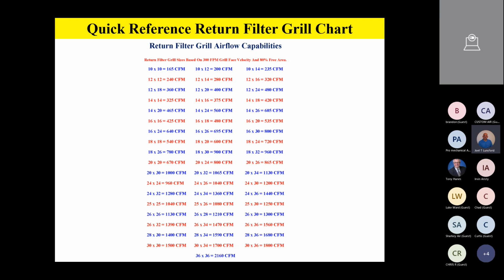of that grill and 300 feet a minute grill face velocity, that's the maximum velocity Manual D recommends for the air moving across the filter. If you've got a filter in that grill, they don't want you exceeding 300 feet per minute across that filter. The higher the velocity, the less efficient that filter works. And so based on all the Manual D criteria I've just mentioned, this is a quick sheet to help you say, well, gee, I wonder how much air a 20 by 20 filter grill is actually moving. In our example here, right out of Manual D, a 20 by 20 filter grill at 300 feet a minute velocity and 80% free area is going to be good for about 650 or 670 CFM. A 24 by 30 would be 1200 CFM and so on.